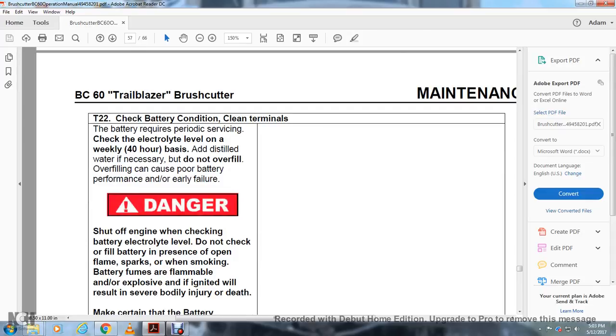T22, check the battery condition, clean terminals. The battery requires periodic servicing. Check the electrolyte level on a weekly or 40-hour basis. Distilled water is necessary. Do not overfill. Overfilling will result in poor battery performance and earlier failure. Danger: shut off the engine when checking the battery electrolyte level. Do not check the battery in the presence of open flame or sparks, or when smoking. Battery fumes are flammable and explosive, and if ignited will result in severe bodily injury or death.